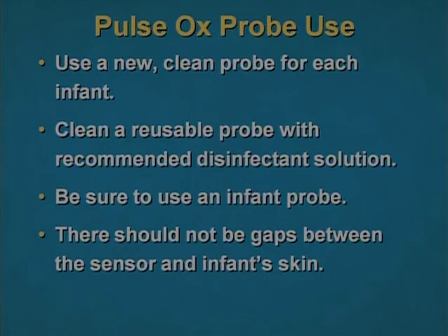It is important to use a new clean probe for each infant if you're using a disposable probe. And if you're using a reusable probe, you should clean it per the manufacturer's recommendations for use of disinfectant solution. You also want to be sure to use an infant probe. There are adult probes and infant probes, so make sure that an infant probe is used when screening the newborn. In addition, there shouldn't be any gaps between the sensor and the infant's skin. So again, just make sure it's secured with the adhesive properly on the hand and the foot.